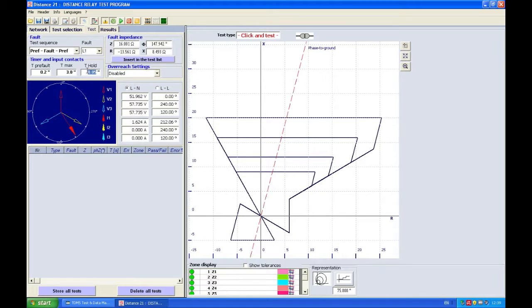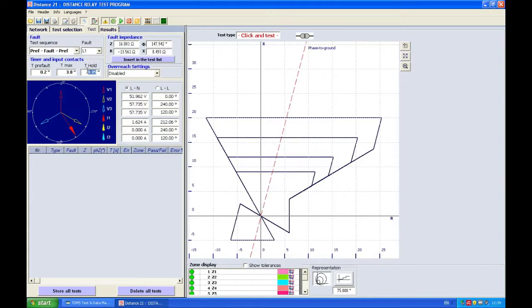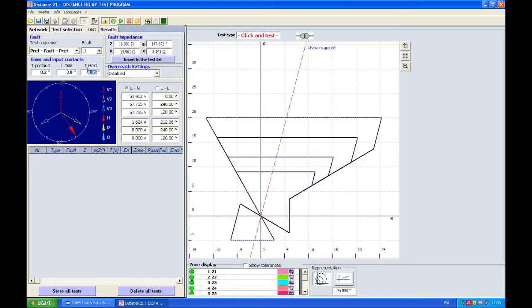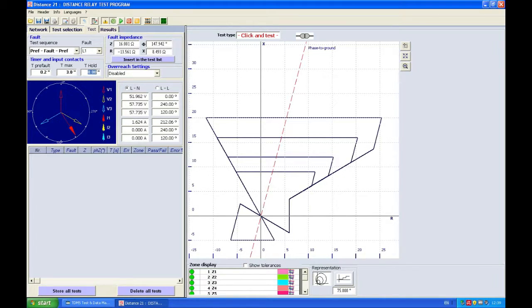This thing here is used to make testing more realistic because the circuit breaker when it receives the tripping command doesn't open instantaneously. It's impossible. It takes about 50, 60, 70 milliseconds for the circuit breaker to open. I will choose to generate 0.0 current after the DRTS receives the tripping signal.